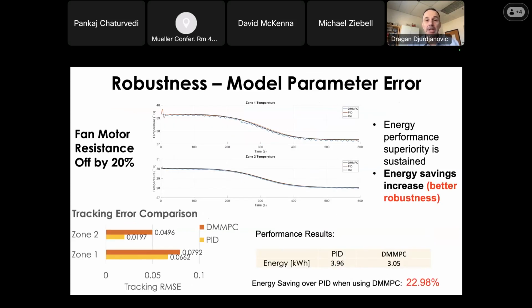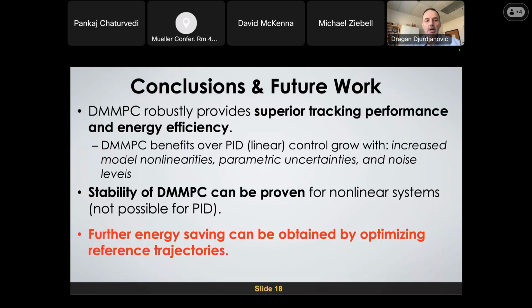tracking. In addition, we actually were pretending like, okay, what if a fault happens? What if our fan motor changed? So resistance increased by 20% in the fan motor at some point. And you can see that our model predictive control adapts to these situations, and energy savings are even bigger with our model predictive control still being able to deliver desired performance. So what is the main message that I want to give to you? Advanced math utilizing model predictive control can give you superior tracking performance with energy savings.